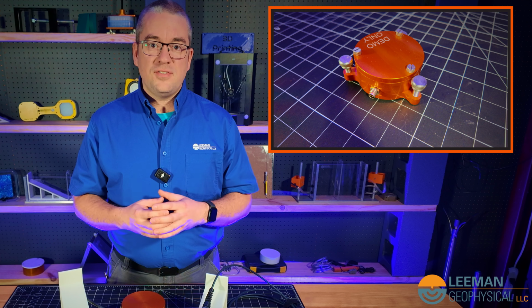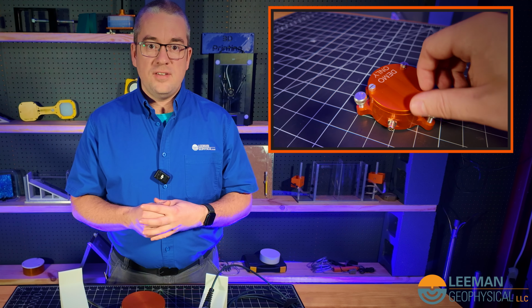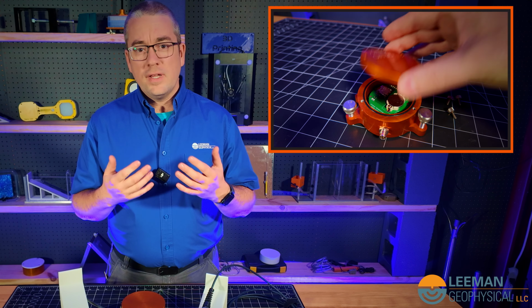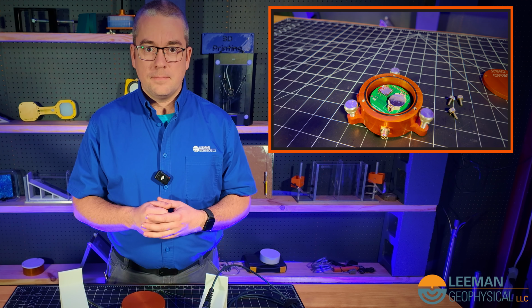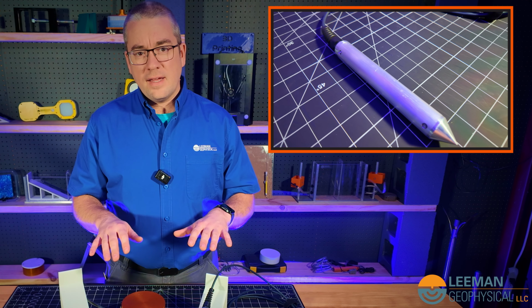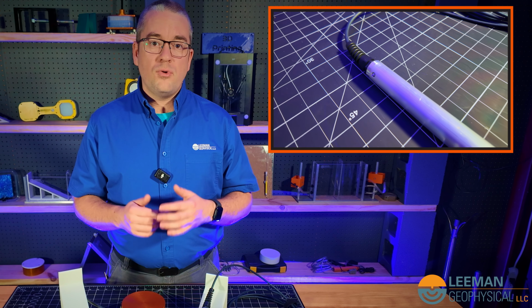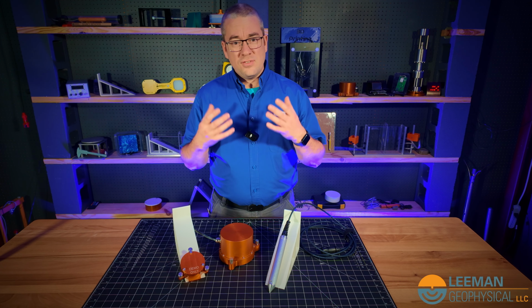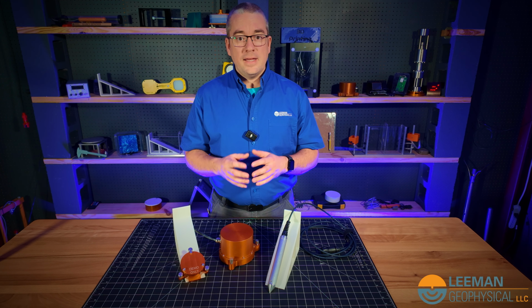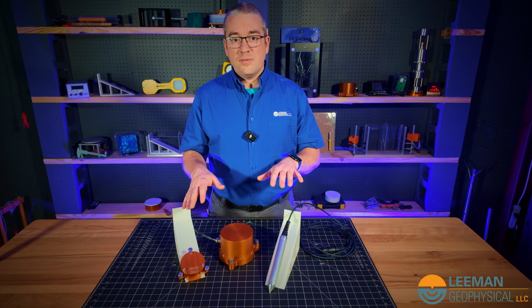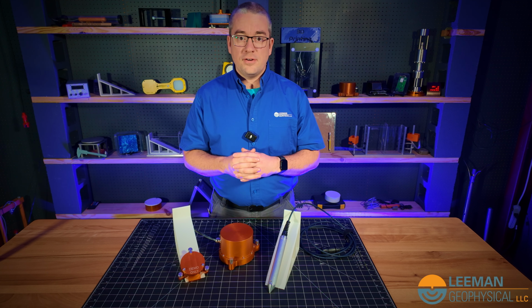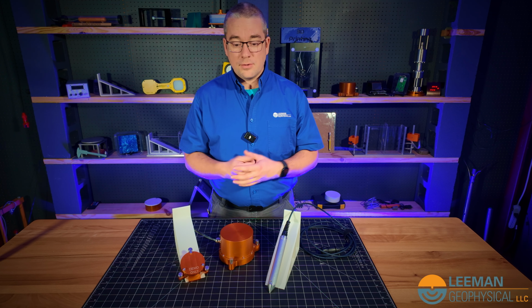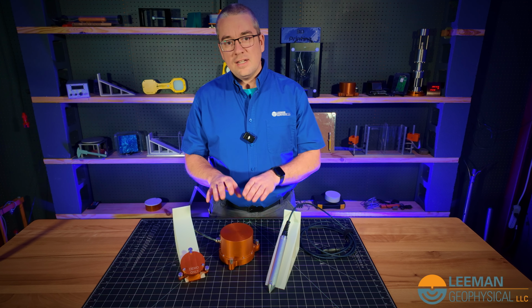MEMS tiltmeters are based on etched circuits on very small pieces of silicon, and they allow us to have really pretty accurate tilt measurements, especially when we're using our differential MEMS technology. Now, MEMS tiltmeters, the ones here anyway, have a resolution of about 1.79 thousandths of a degree. So that's still a very small resolution, and it happens over a pretty large range. We have them available up to plus or minus 90 degrees. Most of the time you're looking at plus or minus 30 degrees, which is still a very large range for geophysical tilts or even environmental and geotech work, but they're not as accurate as an electrolytic sensor.